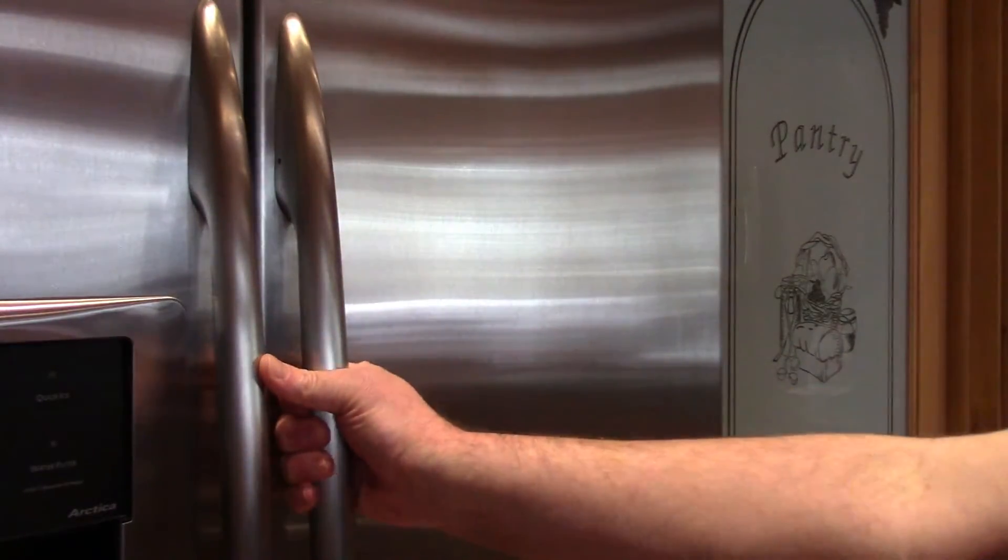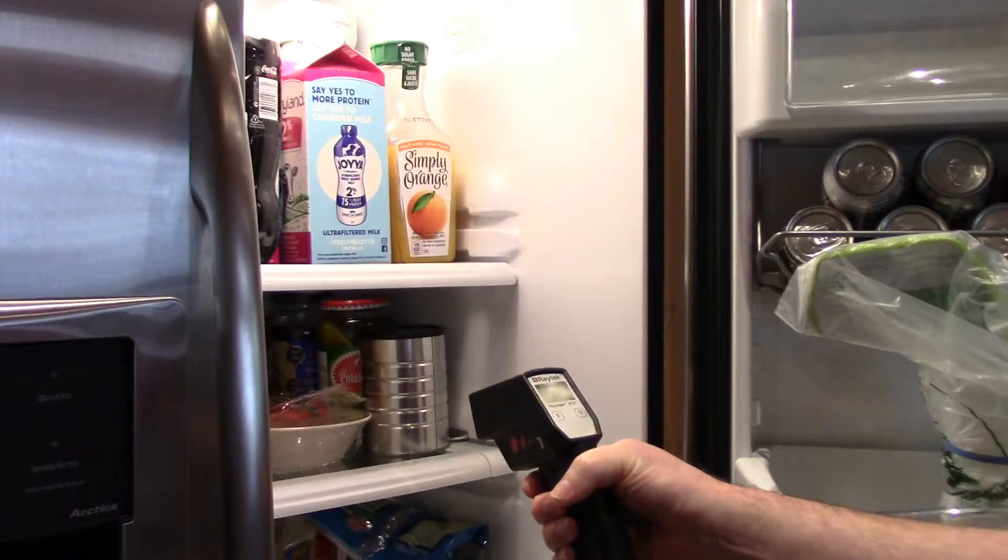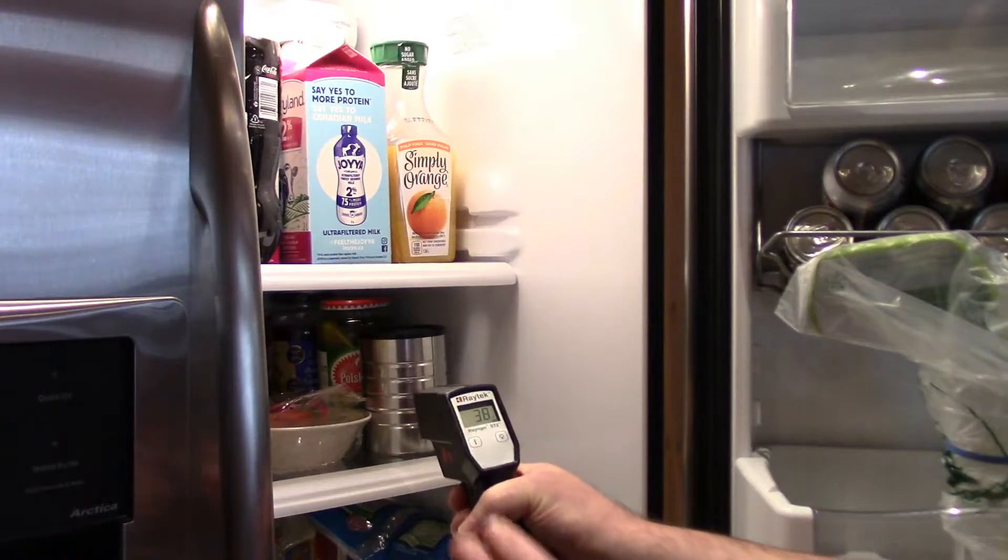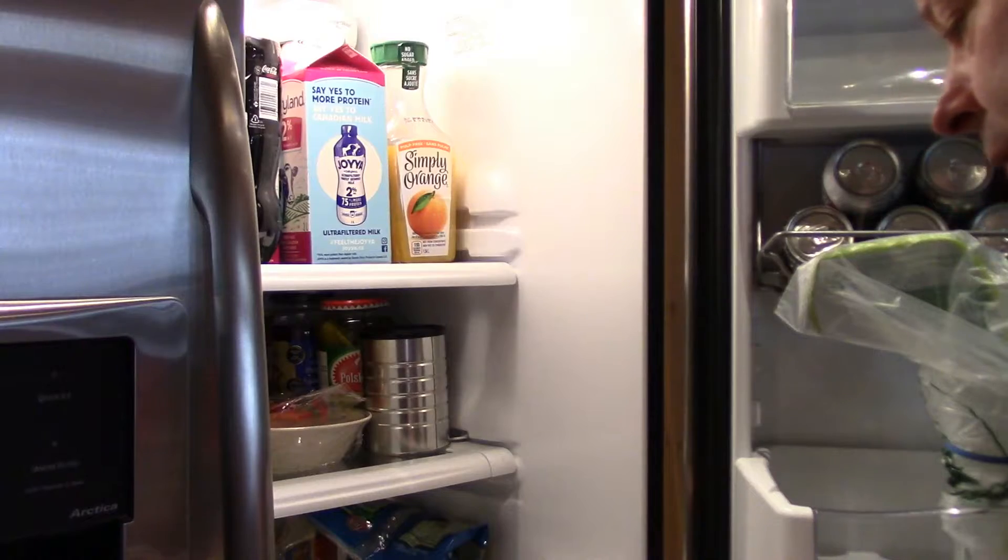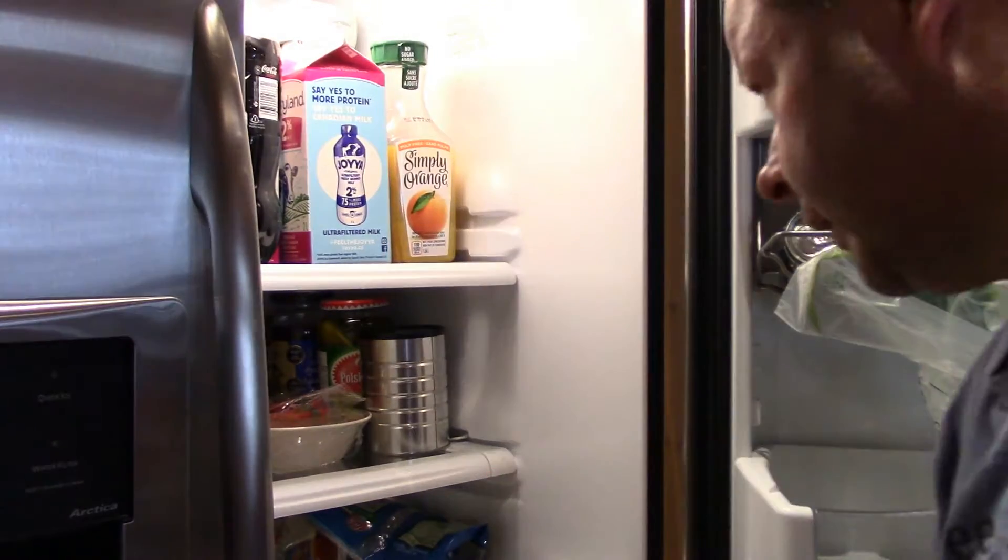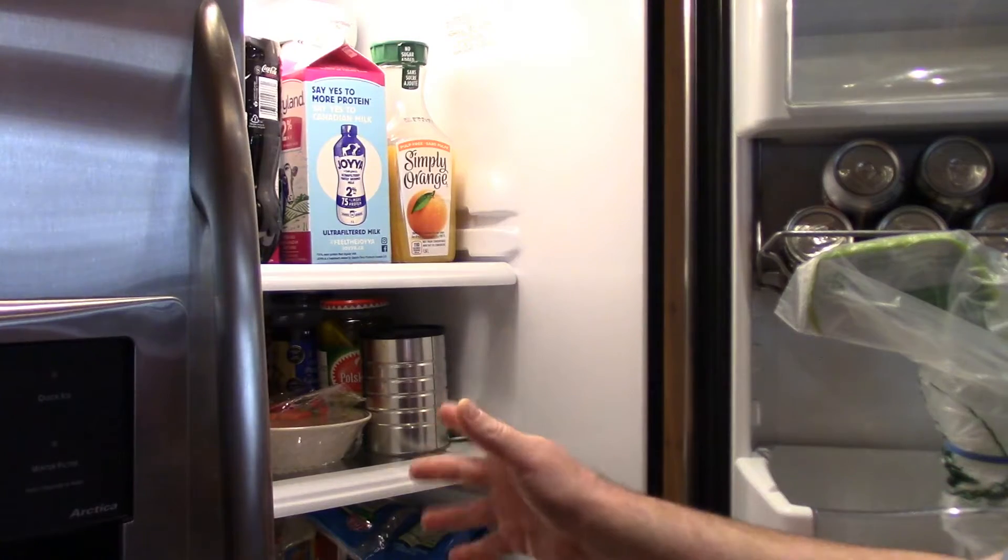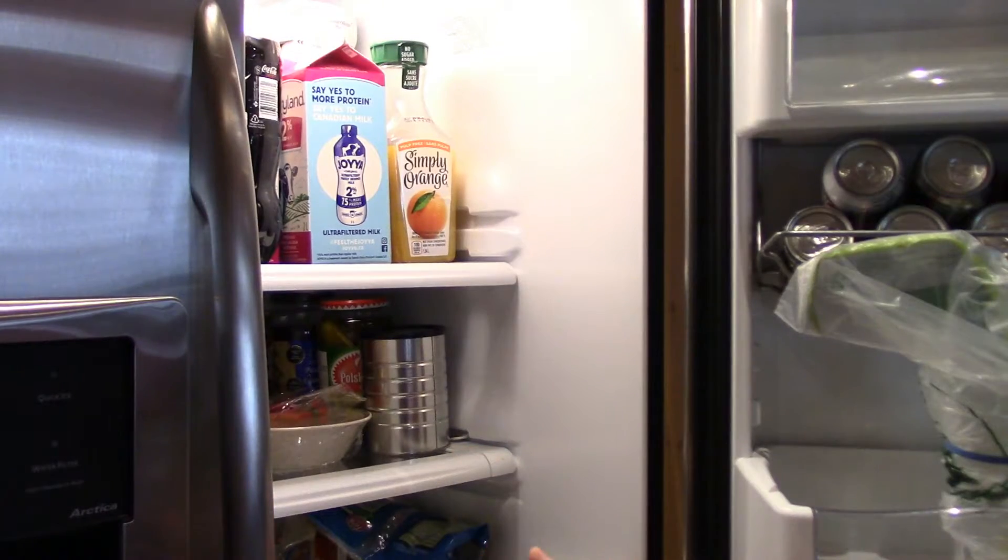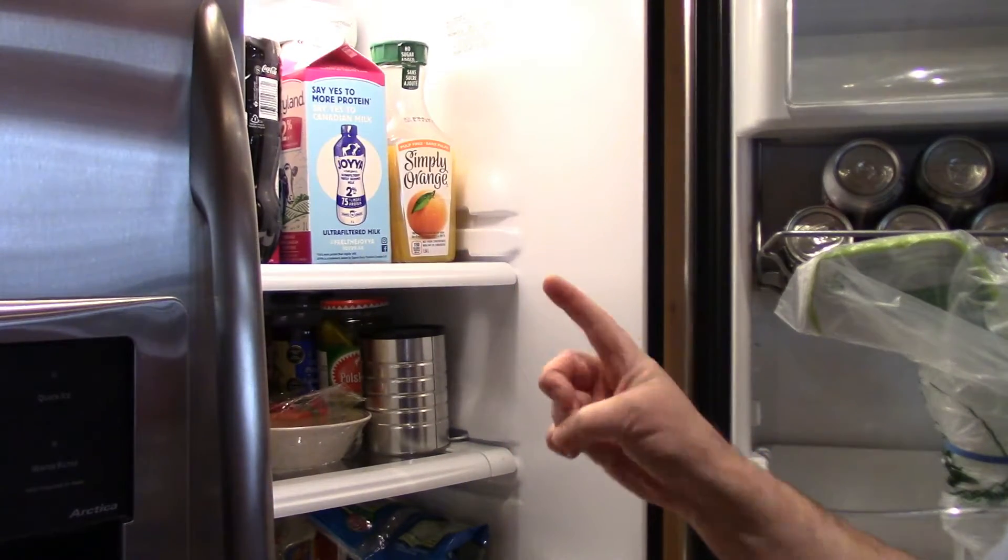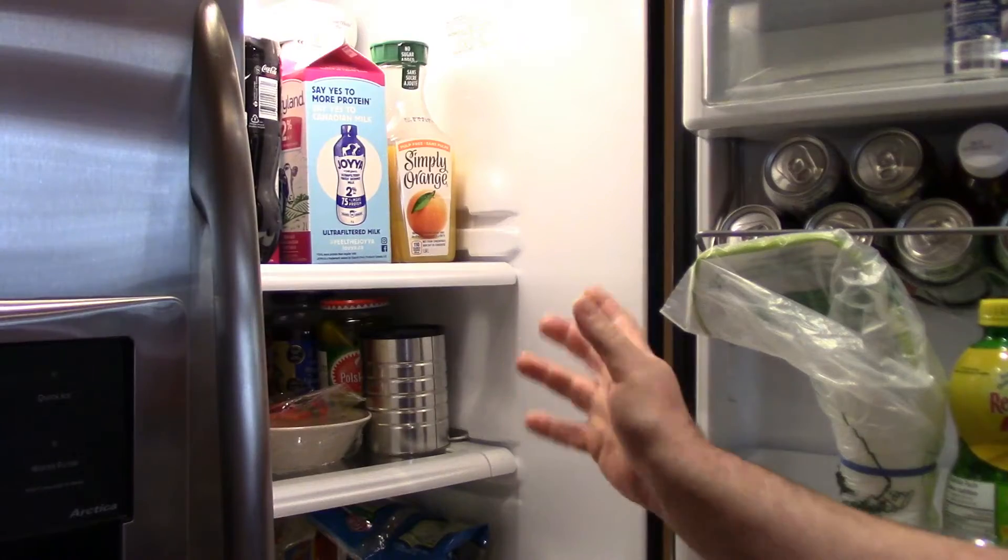It's been about 13-14 hours. Already got it restocked and I think we got our beat here. The temperature set to 37 and we're sitting around 36. Now if this didn't work, probably what I'd do is I'd replace the other temperature sensor on the side here and then if that didn't even work then yeah I'd probably suspect the motherboard. They're not that much, maybe 120 bucks for this particular model. Definitely check those sensors first. They seem to be a known commodity that fails. I'm going to order another one up, maybe even two. It seems every five years. I don't know if that's typical or not.